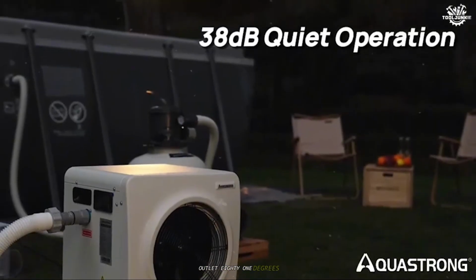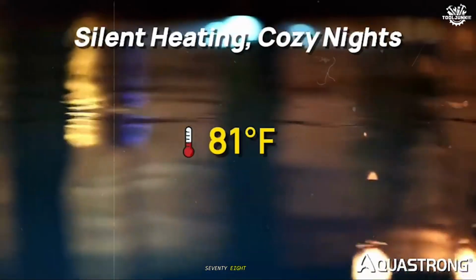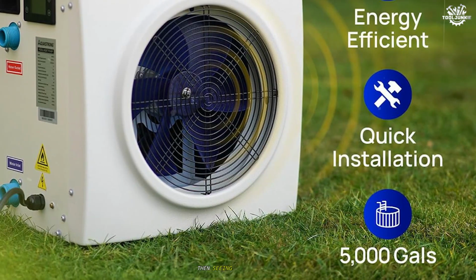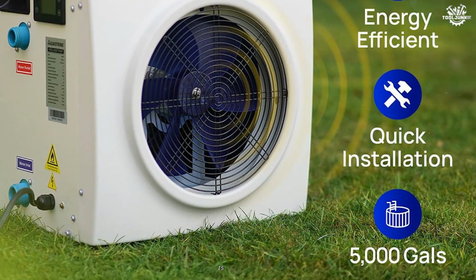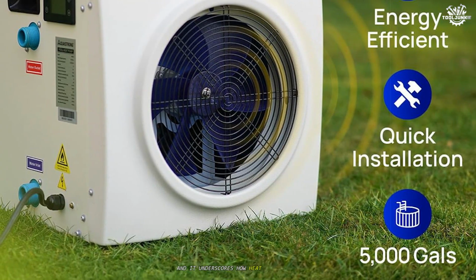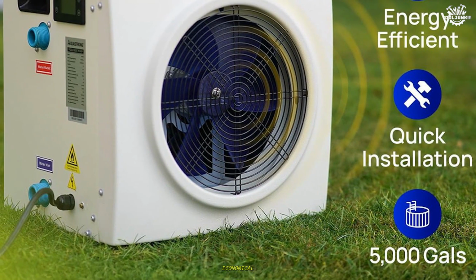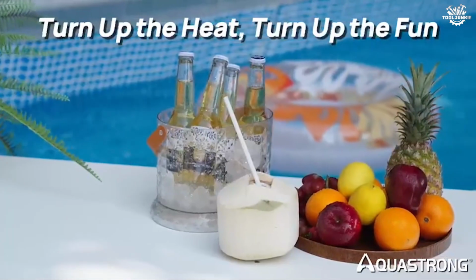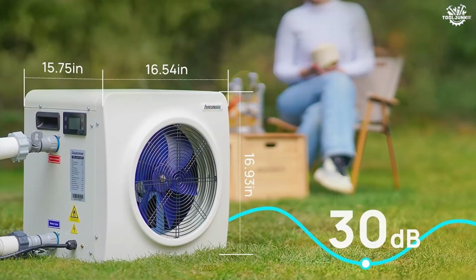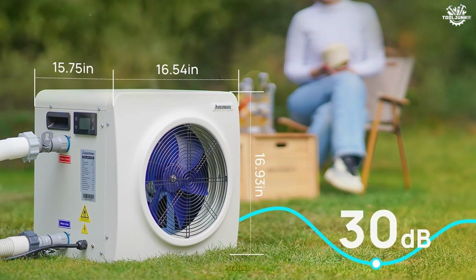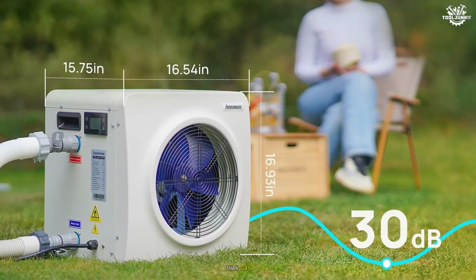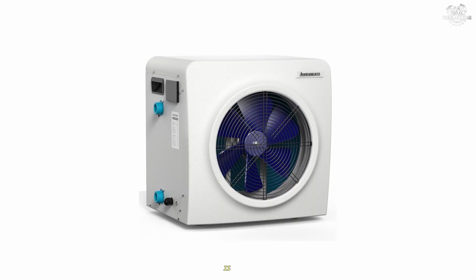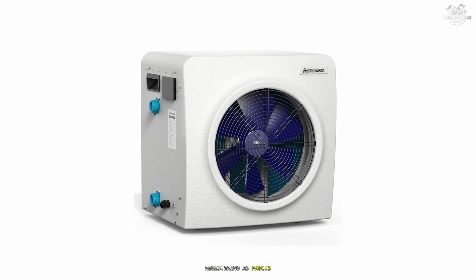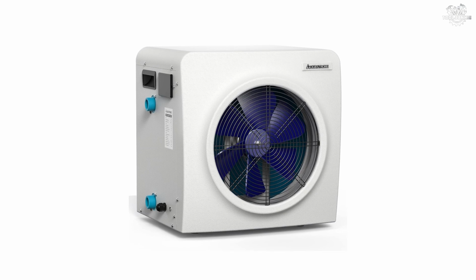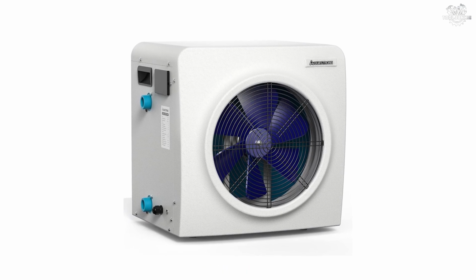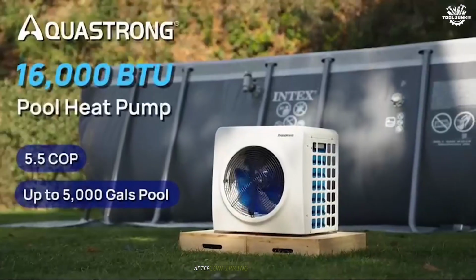Watching outlet 81 degrees Fahrenheit versus return 78 degrees Fahrenheit in real time, then seeing the pool climb day by day, is gratifying, and it underscores how heat pumps excel at steady, economical maintenance rather than sudden spikes. For mild to warm climates, that translates to long, comfortable seasons and a lower utility profile than gas. A quirk some owners mention: safety interlocks registering as faults when the circulation pump is off. It's a protective behavior, not a failure, and can be addressed with settings after confirming proper flow.